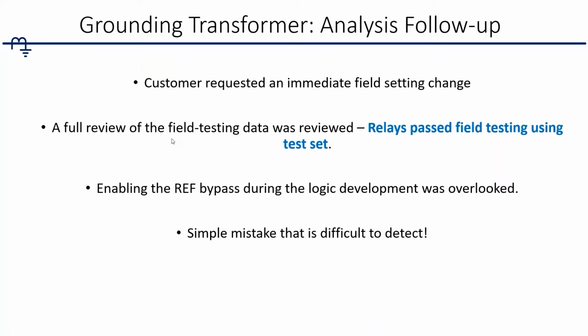But one big thing I took away from this was I took a look at the field testing data after this event occurred, and all the relays passed using a test set. I mean, including myself and 3 other engineers, we missed it as well. And this goes back to what we were saying in the first couple slides, which is that using a test set can sometimes, depending on the complexity of things, give you a false sense of security. This is a more simple example, but I think HIL helps you in that regard. That paradigm shift where you're setting up an actual network level simulation, so you can put faults inside of the transformer, and the phasor relationships and things like that are figured out for you, so you can focus on the logic. So that 1/3 that NERC's reporting, you can focus on getting that down to much less.